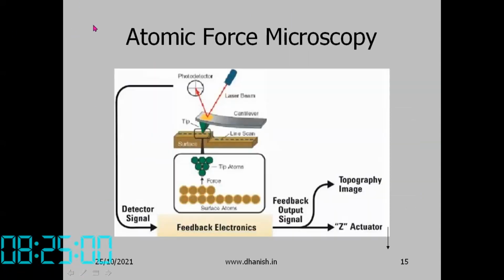Then atomic force microscopy. Once again, it is based on the force between the tip and the surface. So you have to move the tip over the workpiece, and then the force on the tip changes. That is measured. The tip is fixed on a cantilever, and depending on the force, the laser beam, which is reflected to a photodetector, changes its position depending on the attractive force. This goes up and down, and that is used to get the image. So that is the idea of the atomic force microscope.